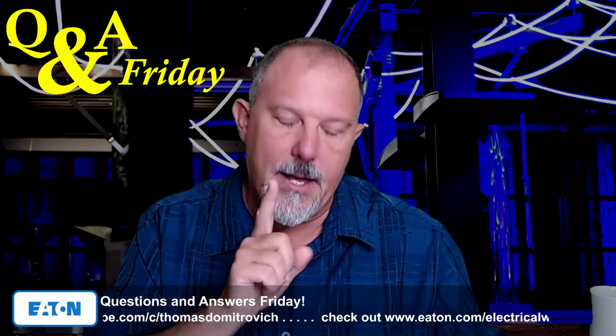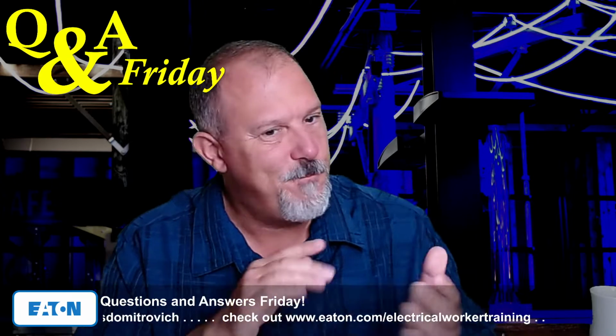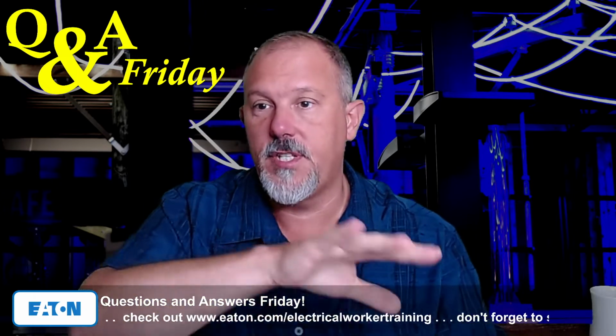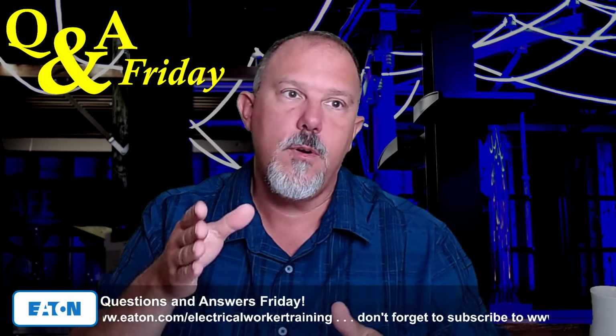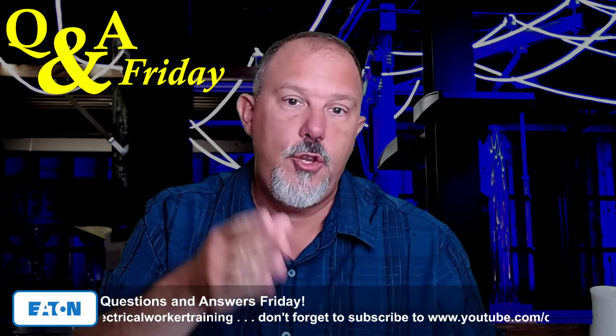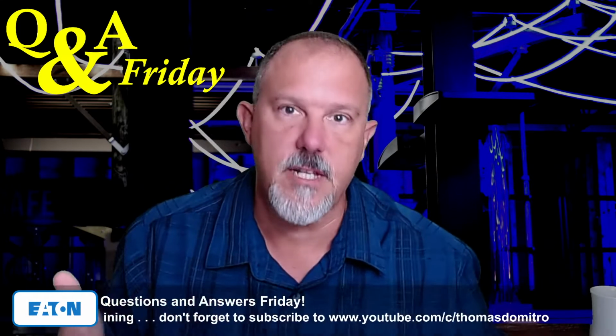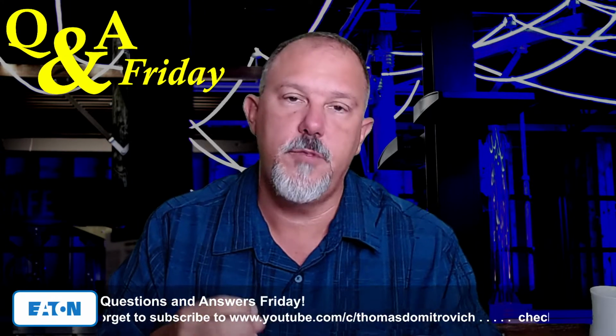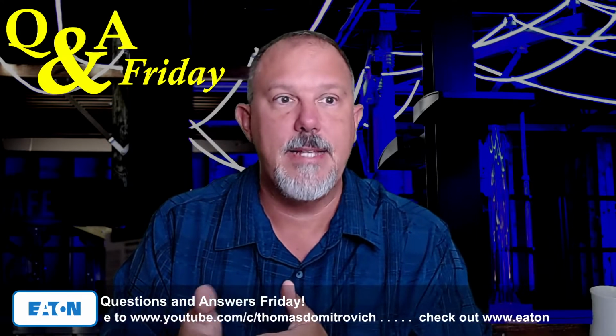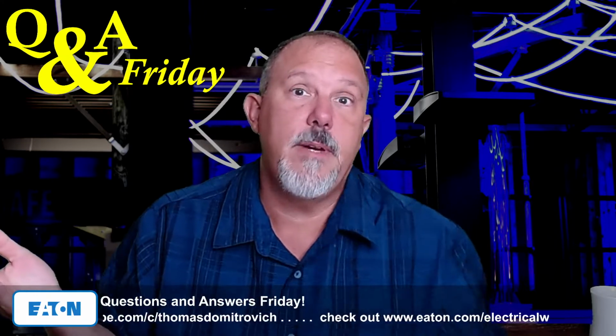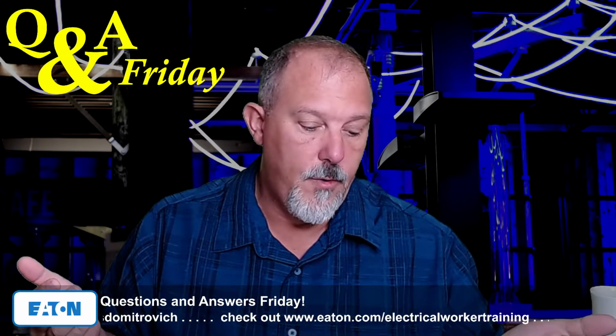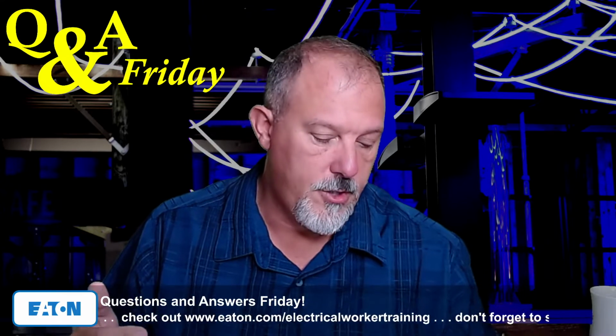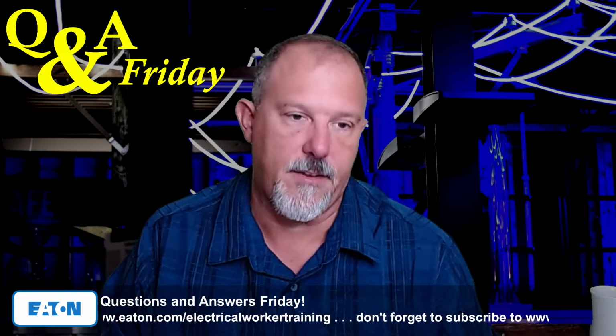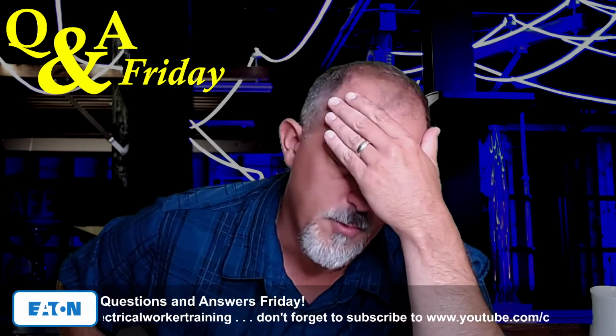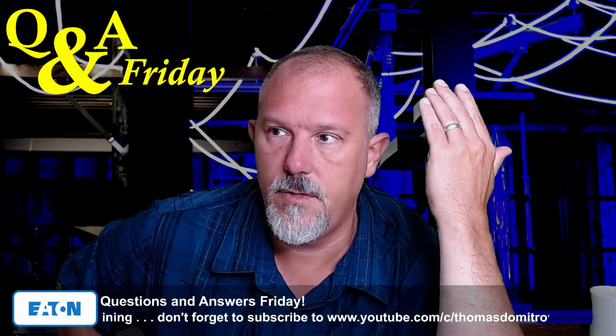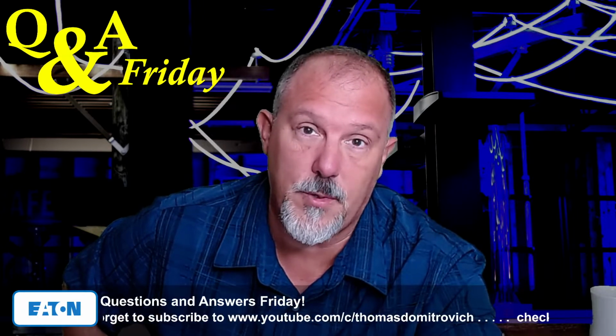Here's the issue. And JW, here's my opinion. Let me just talk to what you said, proving reduction of arcing current. There were submissions that said you could install the product, say it's zone selective interlocking, and the arcing current could be lower than the pickup point for the short time delay set points, and not do anything. You could put an arc reduction maintenance switch on and it won't do anything. You could do differential relaying and it won't do anything. And what did you gain out of it? So it was hard to argue against saying you should make sure that it does what you say it does.